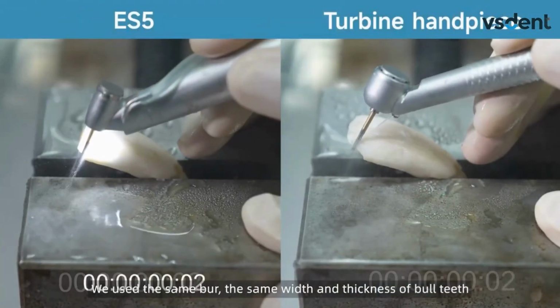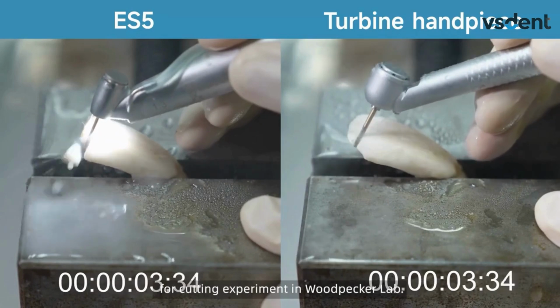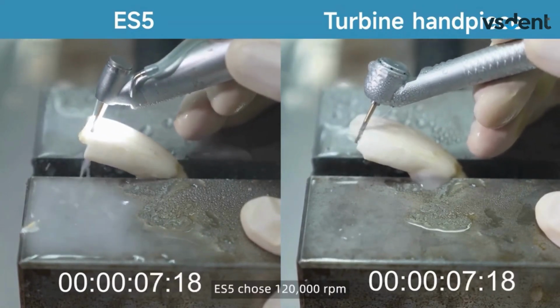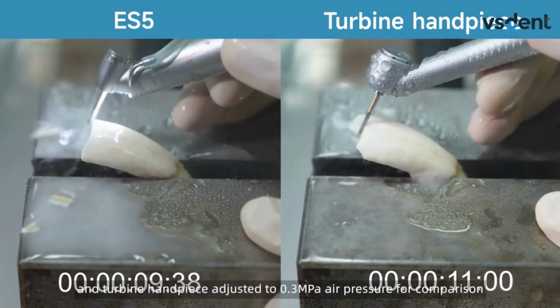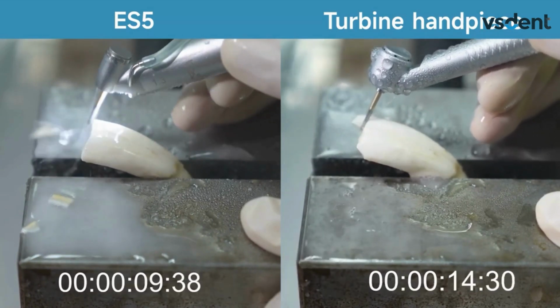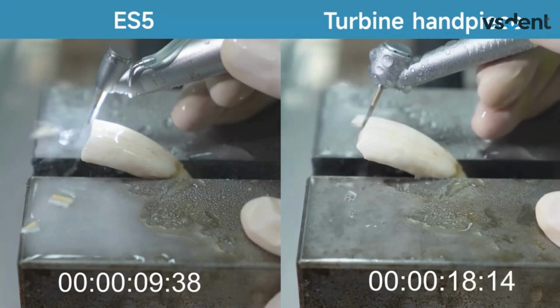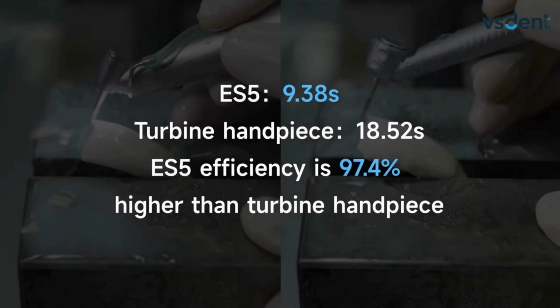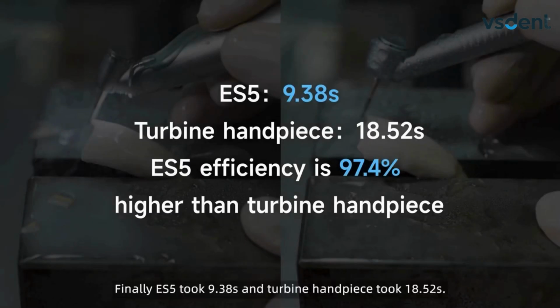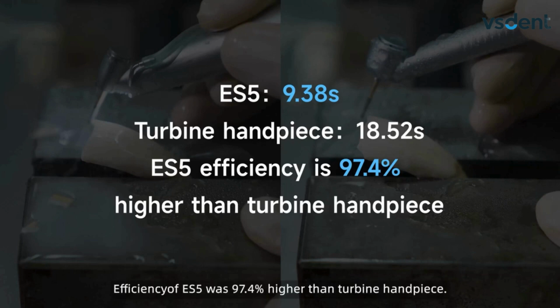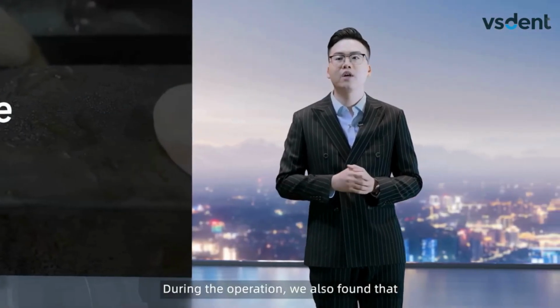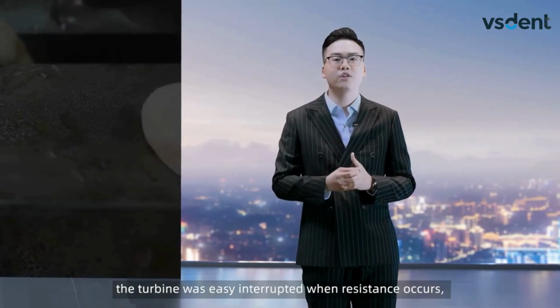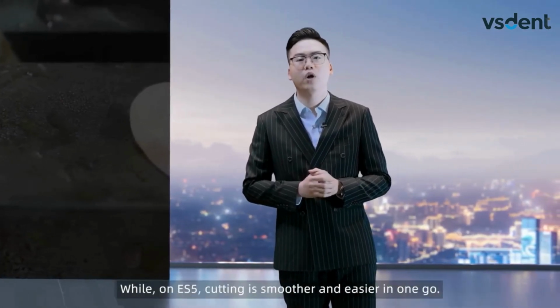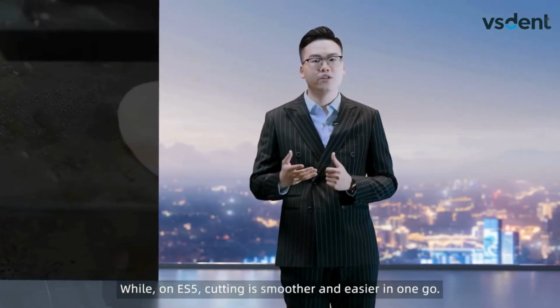We use the same burr, the same width and thickness of bovine teeth for the cutting experiment in the Woodpecker lab. ES5 is set to 120,000 RPM and the turbine handpiece is adjusted to 0.3 MPa air pressure for comparison. Finally, ES5 took 9.38 seconds and the turbine handpiece took 18.52 seconds. The efficiency of ES5 was 97.4% higher than the turbine handpiece. During the operation, we also found that the turbine was easily interrupted when resistance occurred, which required more experience from doctors, while on ES5, cutting is smoother and easier in one go.